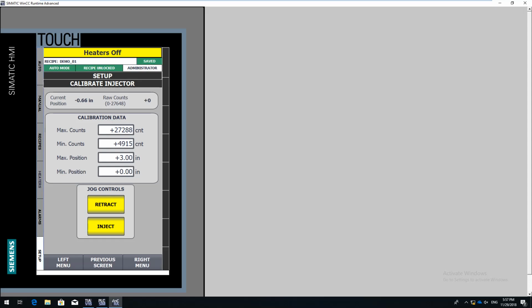To calibrate the system, the best thing to do is drive the injector to some known position. For example, an injector, we can drive it all the way down, which would be 0 position, which in this case we're showing a minimum position of 0. At that point, I would look at the raw counts being read back by the linear pot and type that in on the minimum counts.